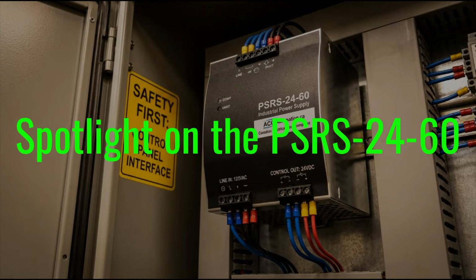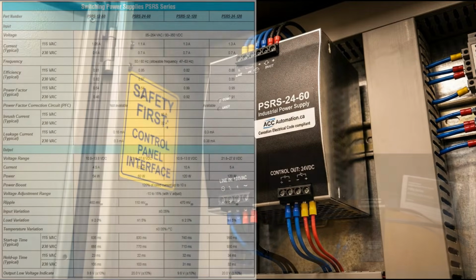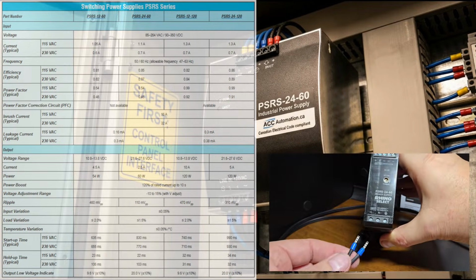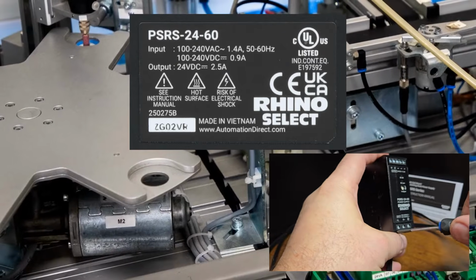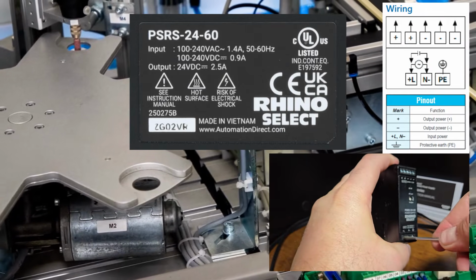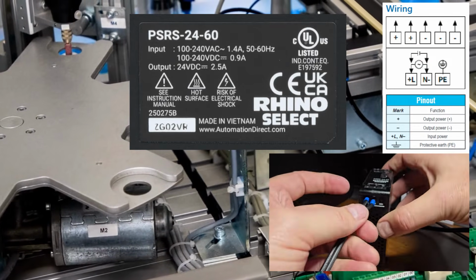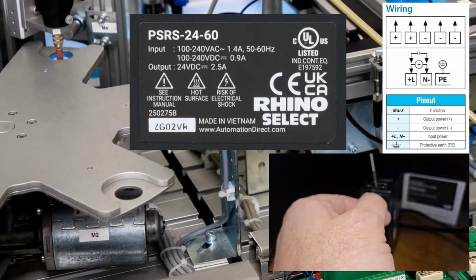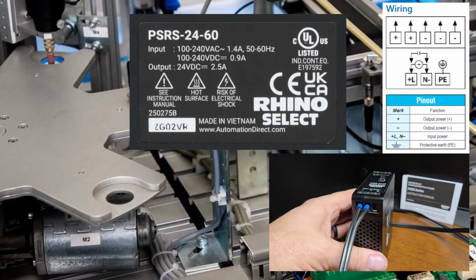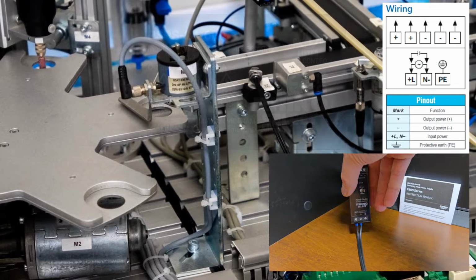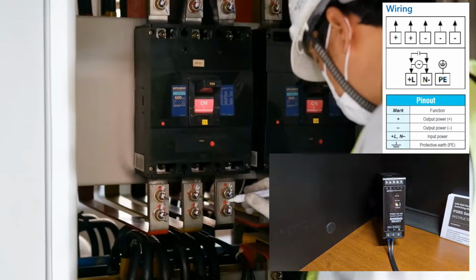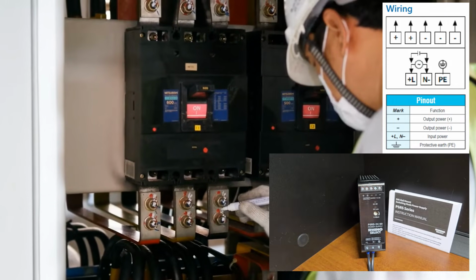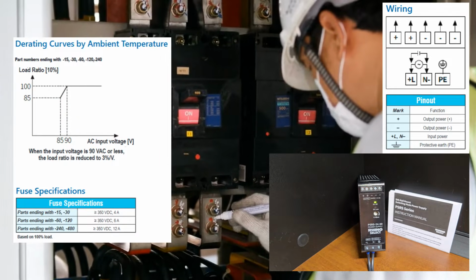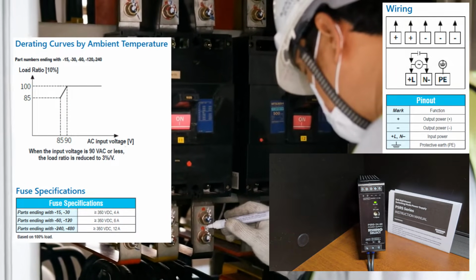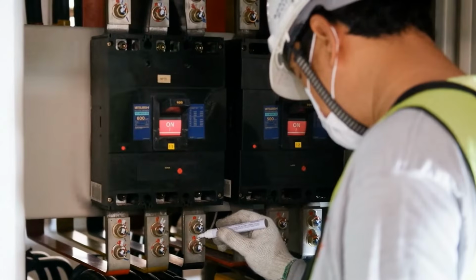Spotlight on the PSRS 2460. The PSRS 2460 is designed specifically to sit in that critical gap between line power and control power. As a 24V DC, 60-watt supply, it occupies a sweet spot for many industrial applications. It provides enough power to run a standard PLC CPU, several input-output cards, and a handful of field sensors without being overly bulky or expensive. Designed for DIN rail mounting, it integrates seamlessly into standard cabinet layouts, providing the necessary isolation and regulated DC power that keeps processes running smoothly without interruption.